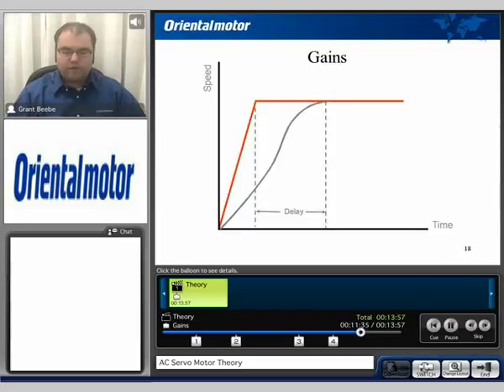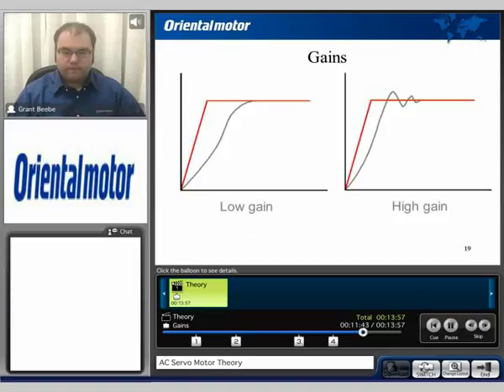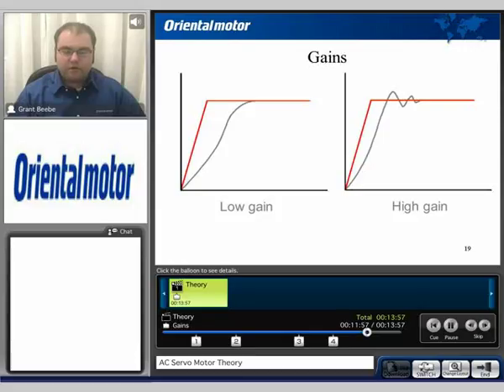What could have taken maybe 50 milliseconds may now take 150 milliseconds — that's the difference between low gain versus high gain. Of course, these can be overcome by doing what is called gain tuning. Typically, you can tune in a servomotor based on a specific application to run in the desired range that you find suitable.